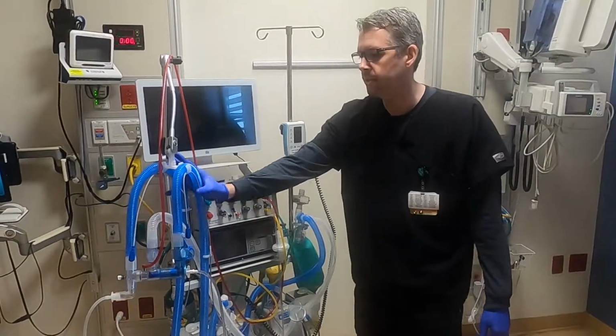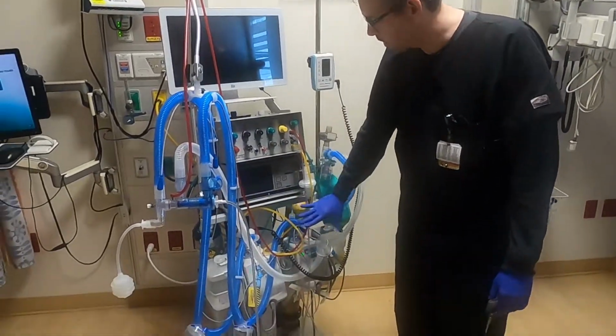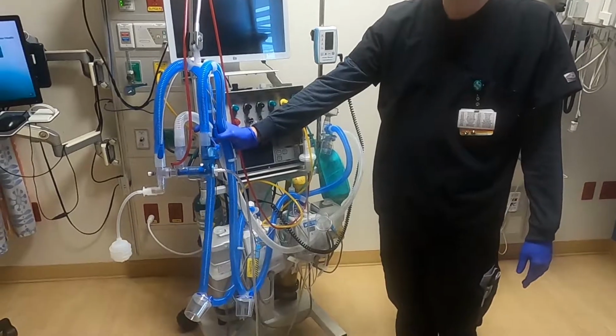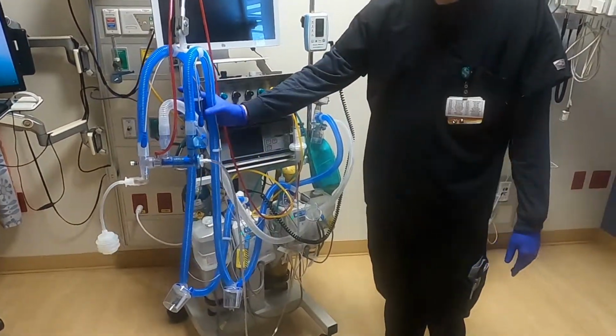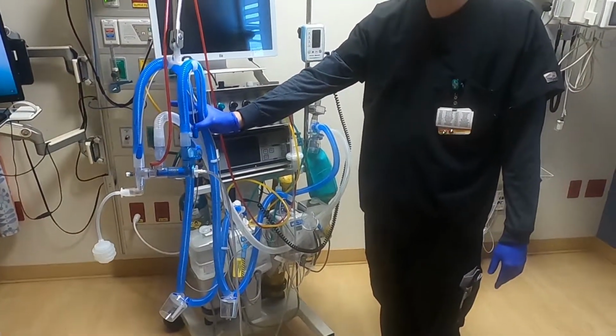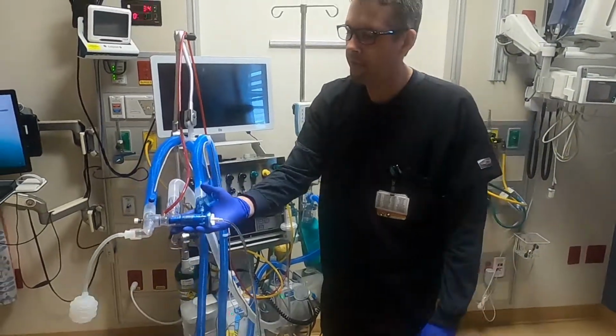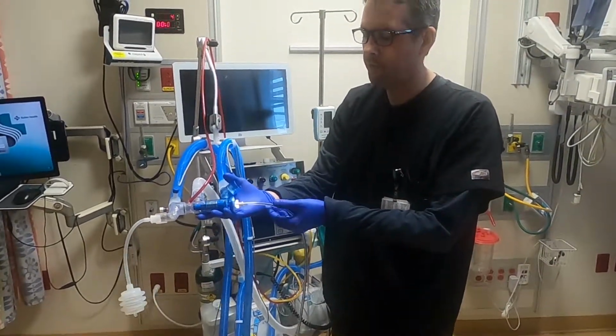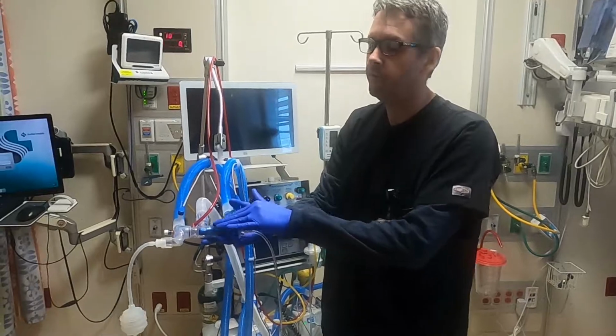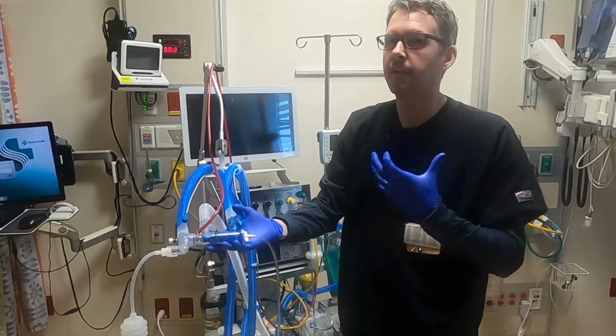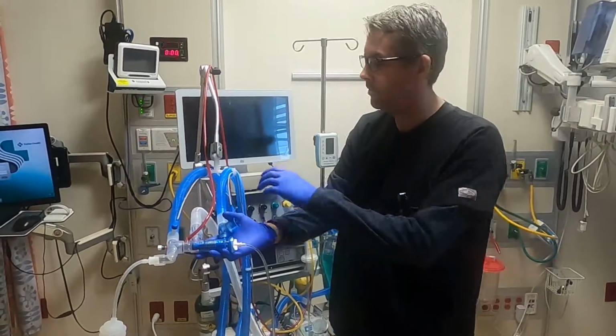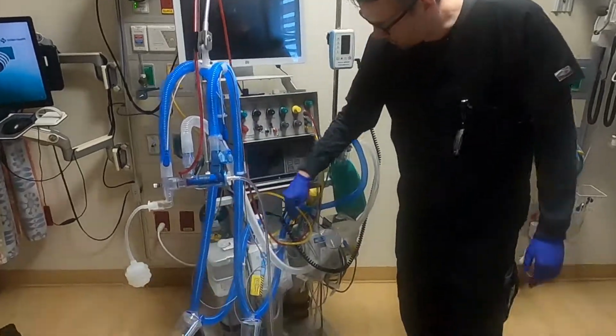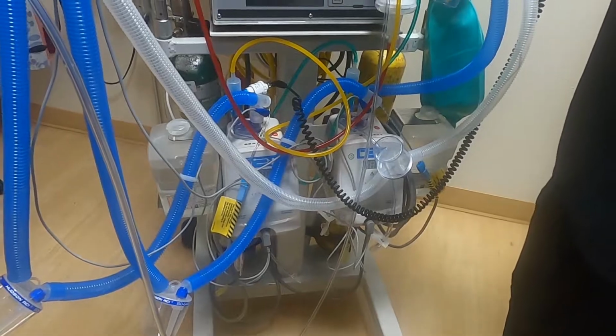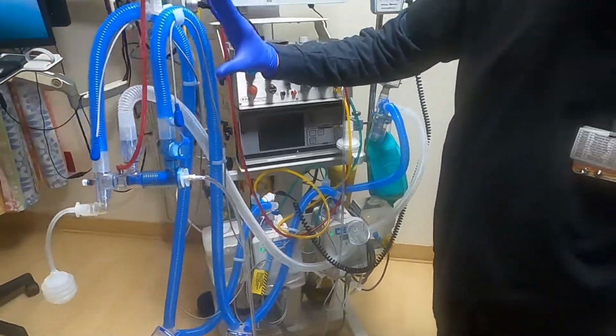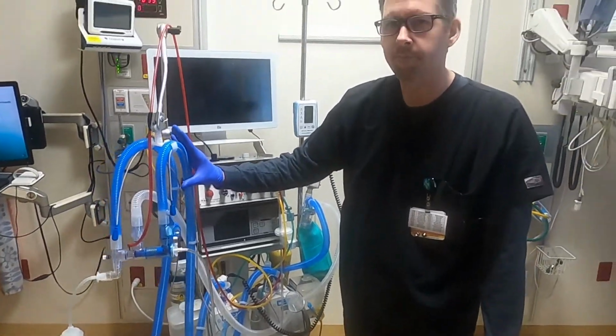The rest of this is basically for heat, humidification, and a little bit of extra flow if the patient needs it. One of the things about this machine, it's all flow and pneumatic, so there's a lot of flow that goes through here. The patients can get very dry, so that's why we have two heaters with all of our setups here to provide a really high amount of humidity to make sure the tubes don't plug off.